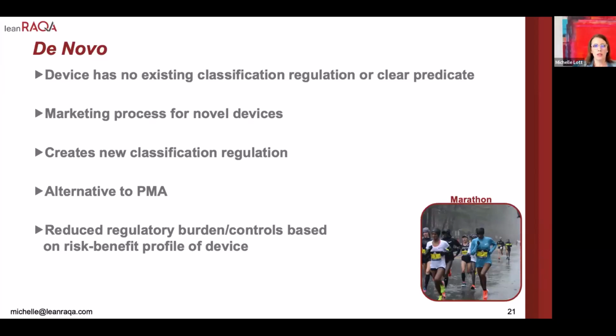And you use the intended use to guide you to picking the regulation that best fits your intended use statement and product features. That's another unique thing about the US compared to the EU and other markets, because those are generally more rule-based, and it's just a handful of rules, not specific to drilling down to thousands of different product types like the US does.